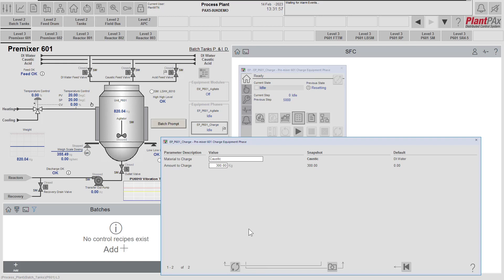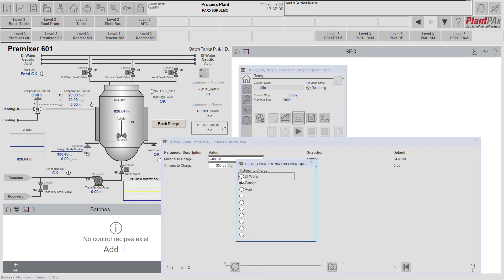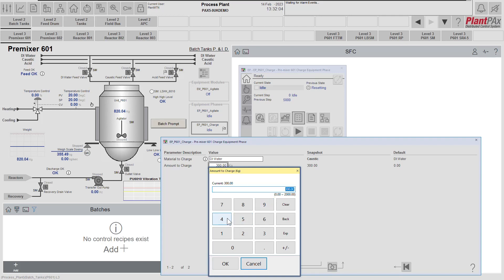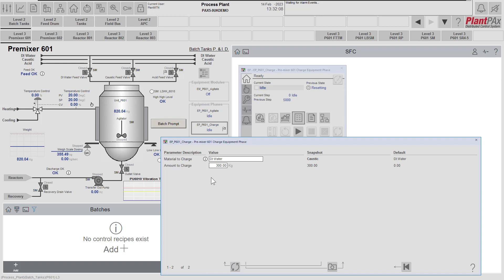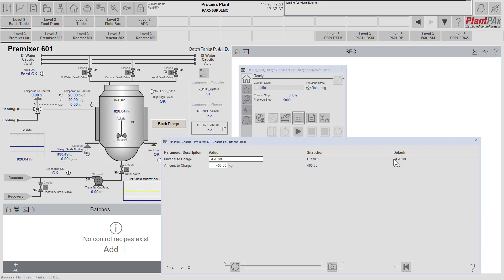So let's set up this equipment phase to charge water into our pre-mixer. I'm going to select DI water and say let's charge 400 kilograms of water. You can see that the faceplate is showing us that these parameters are not currently matching the snapshot values — the snapshot values are the values that the equipment phase will use while it's running. So let's load these values into the snapshot so they will be used by the equipment phase. The implementer has also set up default values for these parameters, which I can apply using this button if I wish.